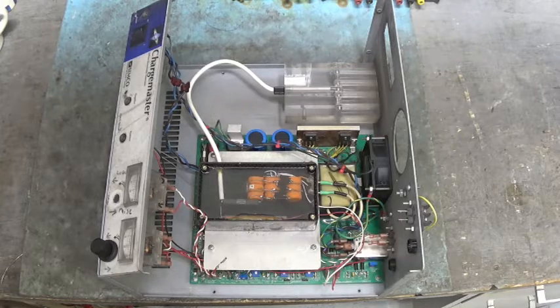When we do our measurements, I use a high voltage probe. You can't measure these high voltages with a standard probe; you have to use a high voltage probe. And I don't look at these voltages with an oscilloscope—I don't have a probe high enough to protect that oscilloscope from that high voltage. So I never put an oscilloscope on this stuff either. I'll show you that high voltage probe here in just a little bit.